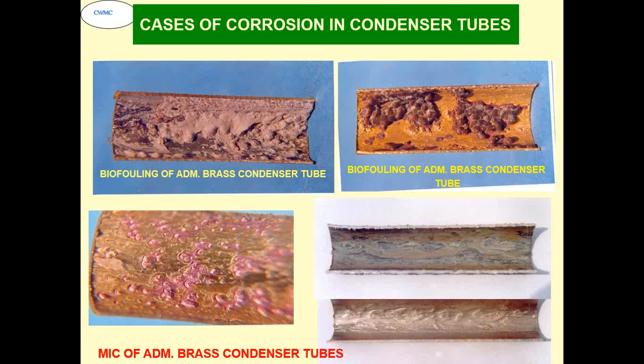A typical biofouling in a river water system is what you see in this picture. On top of this there was a calcium carbonate scale which was mechanically removed. So this is the condition we saw, and this is after chemical cleaning of the same tube. You can see a chain-like structure, which has been formed because of microbiologically induced corrosion below the deposit.